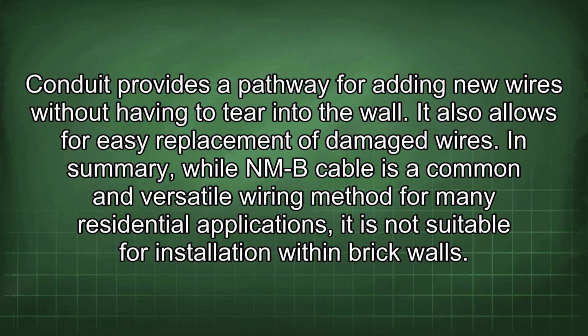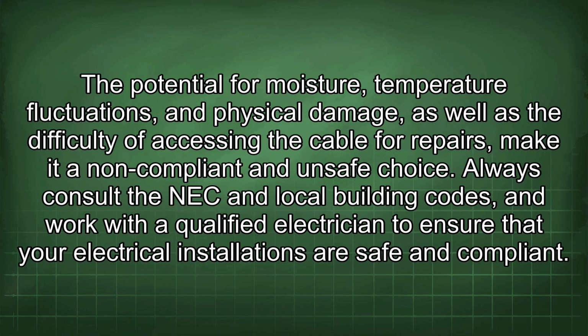In summary, while NMB cable is a common and versatile wiring method for many residential applications, it is not suitable for installation within brick walls. The potential for moisture, temperature fluctuations, and physical damage, as well as the difficulty of accessing the cable for repairs, make it a non-compliant and unsafe choice. Always consult the NEC and local building codes, and work with a qualified electrician to ensure that your electrical installations are safe and compliant.